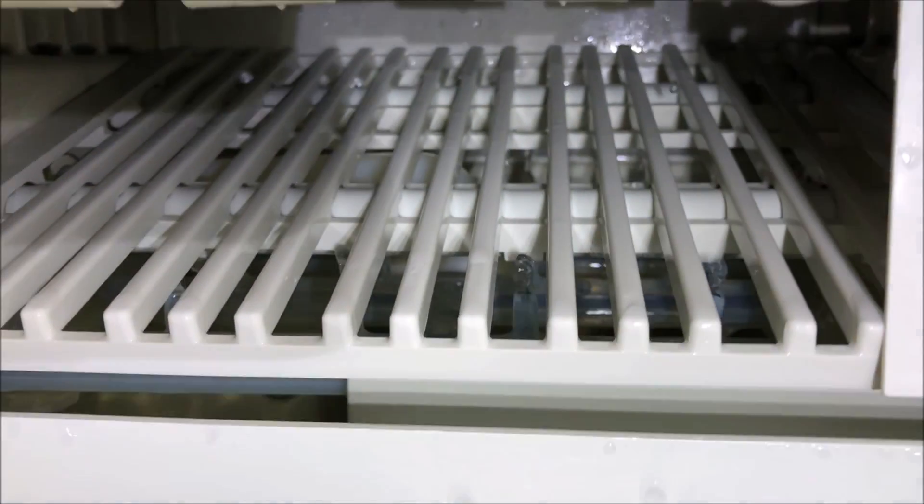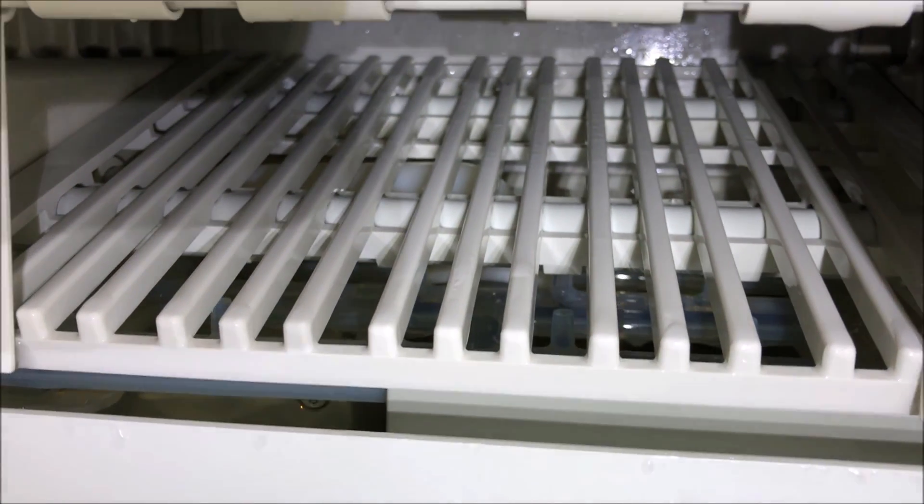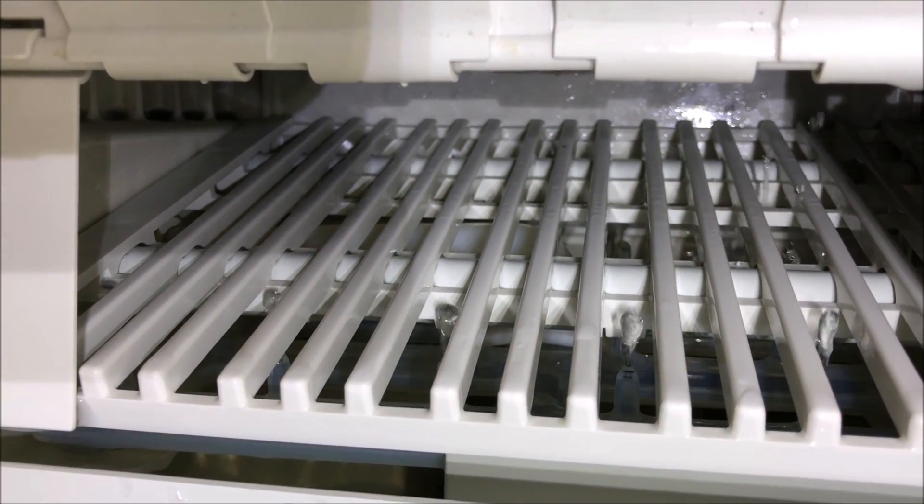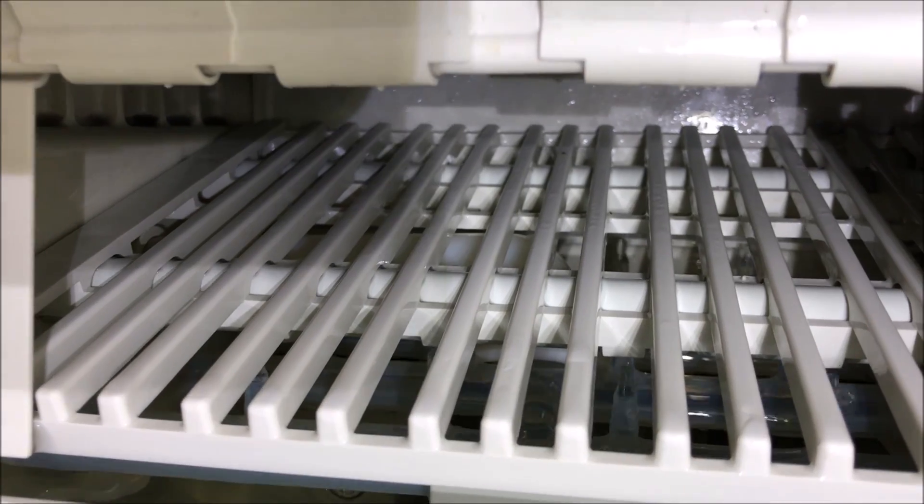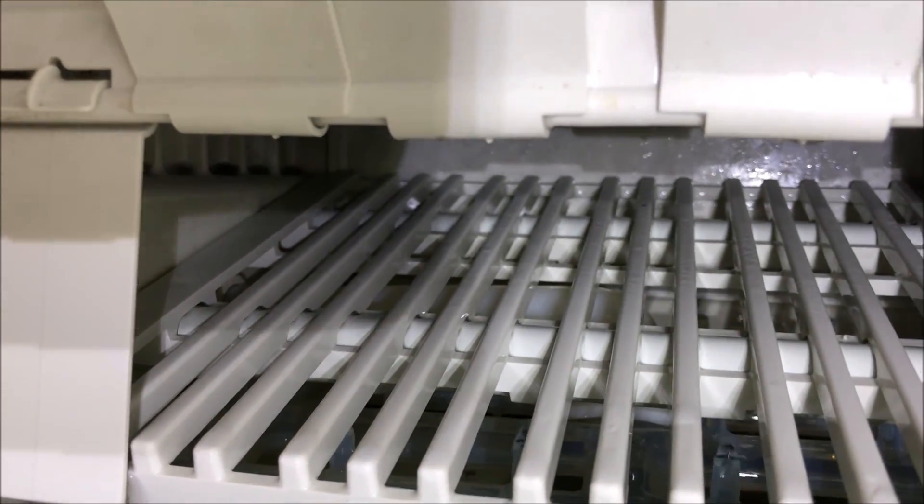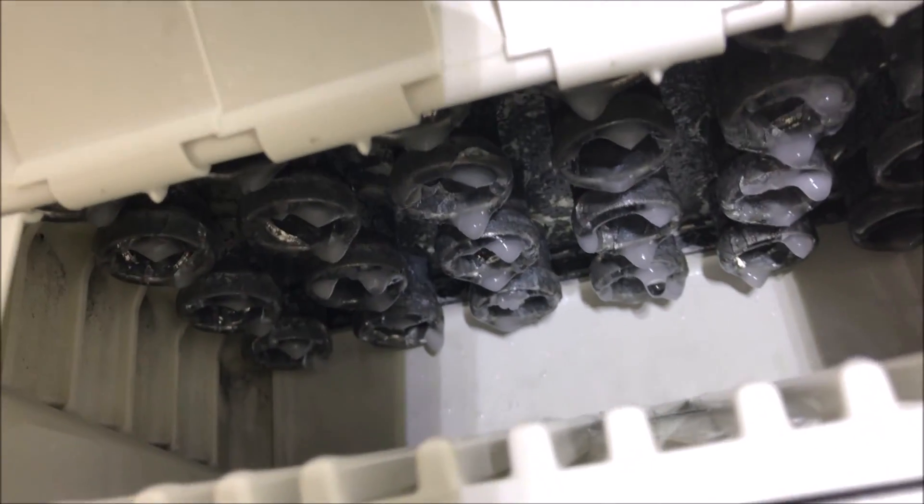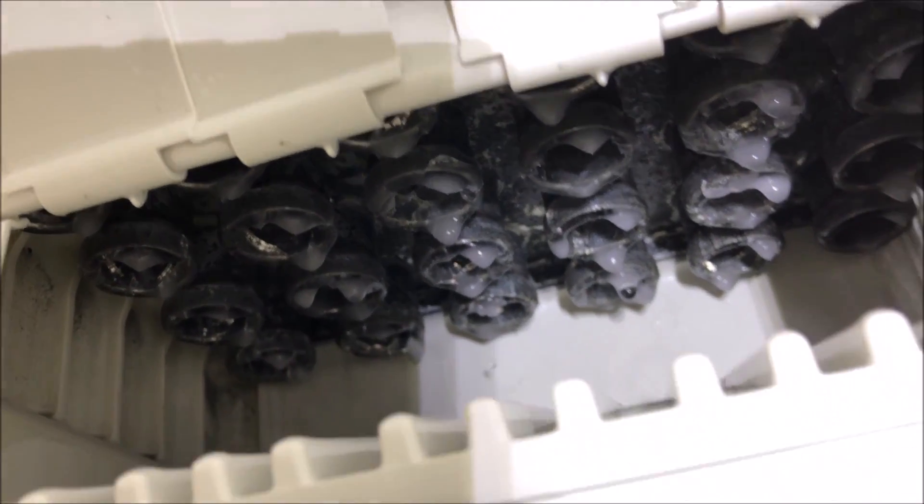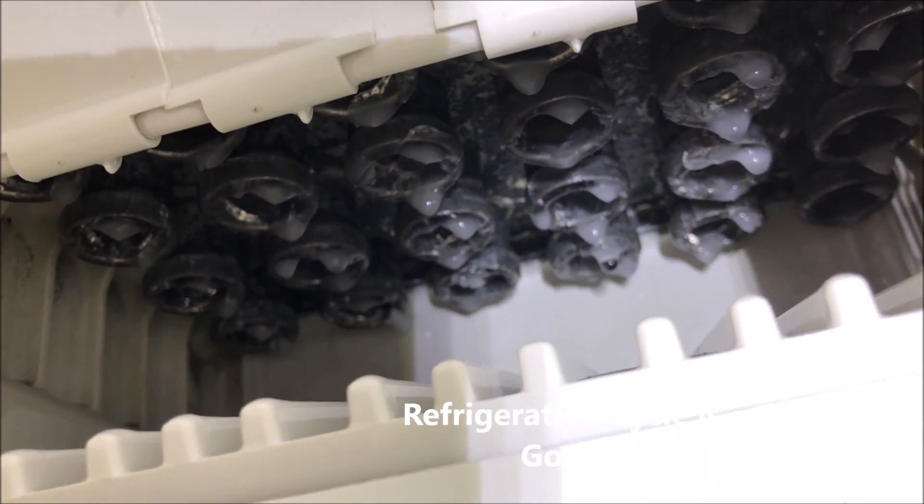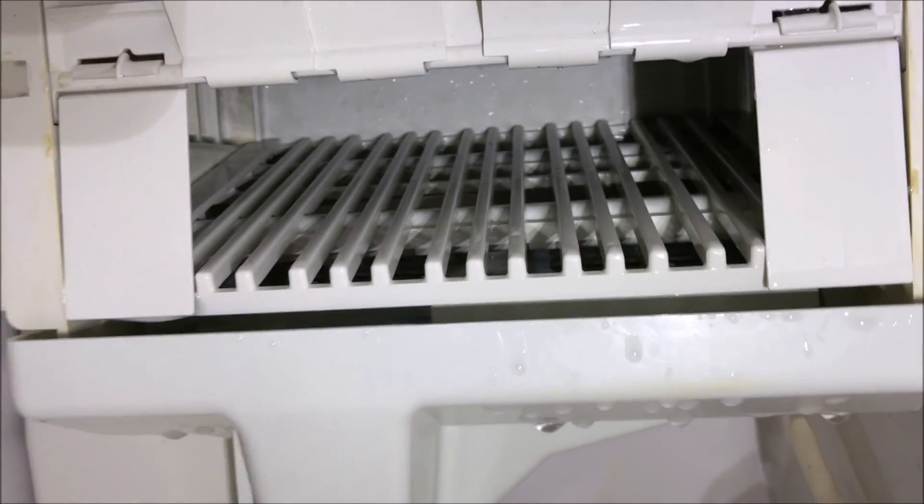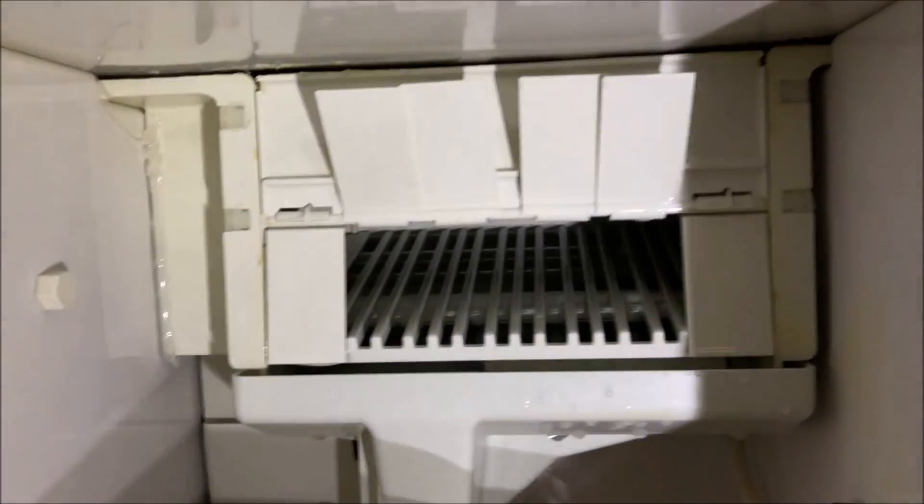Let's take a look here. There's barely any water running out of this pump. Well we can see at least the evaporator coils freezing up which is a good sign. So we most likely have a water issue here.